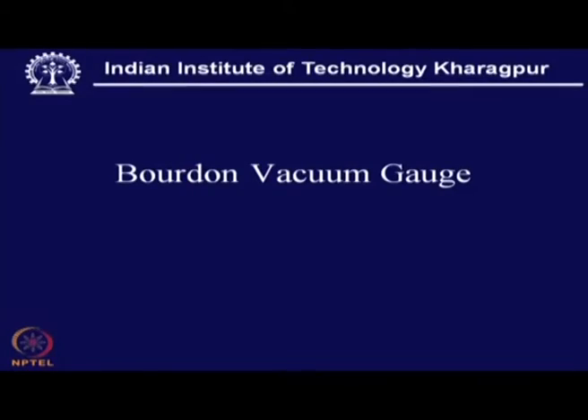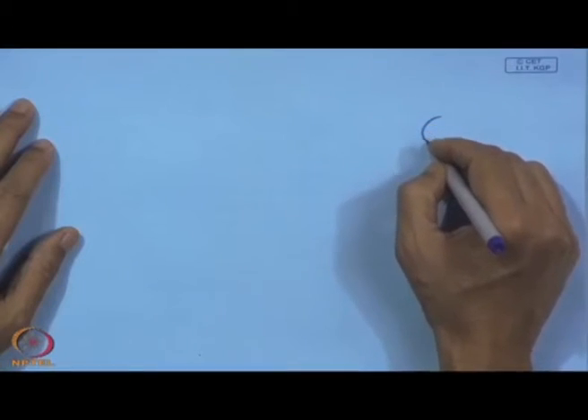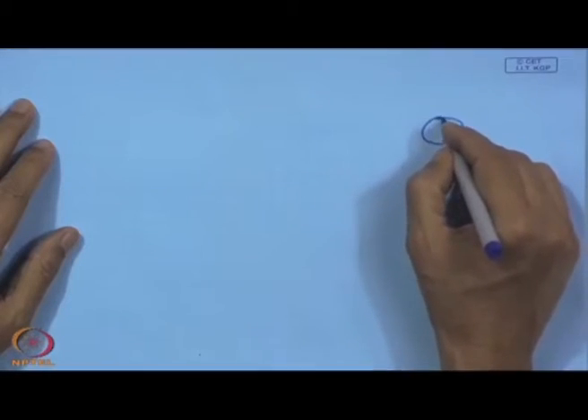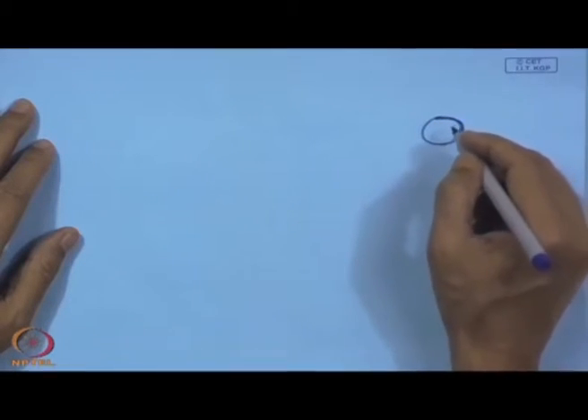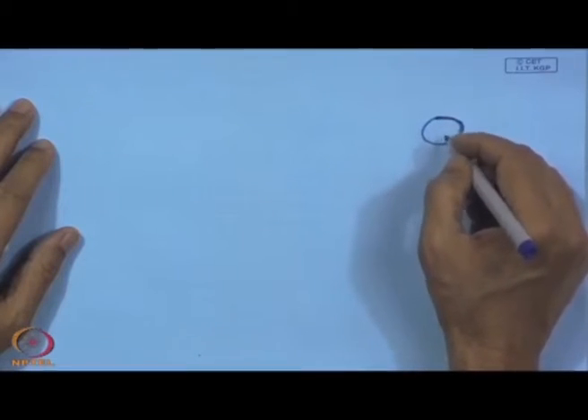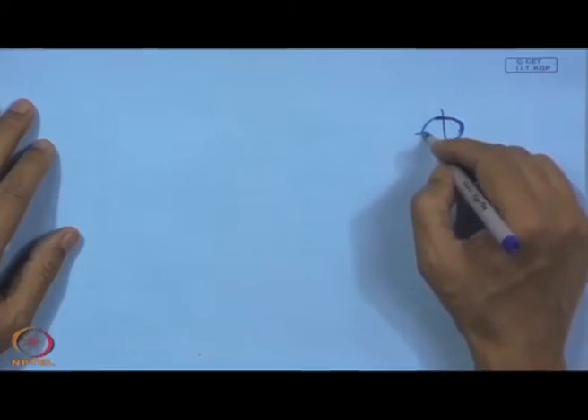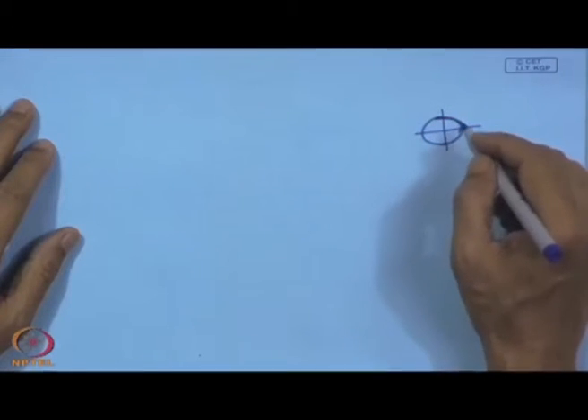Now, here we see the very basic and fundamental Bourdon vacuum gauge, and schematically we can show this. This is nothing but a circular tube which is made into an elliptical tube in this shape, and this tube changes its shape and dimension when some change in pressure occurs within it.